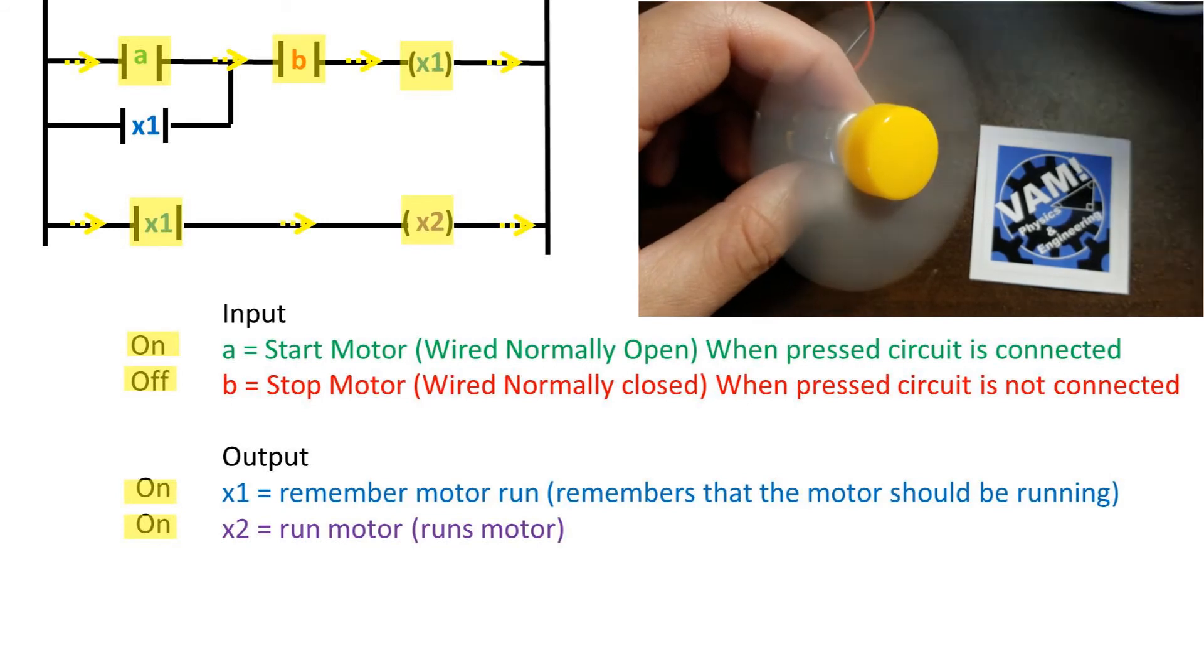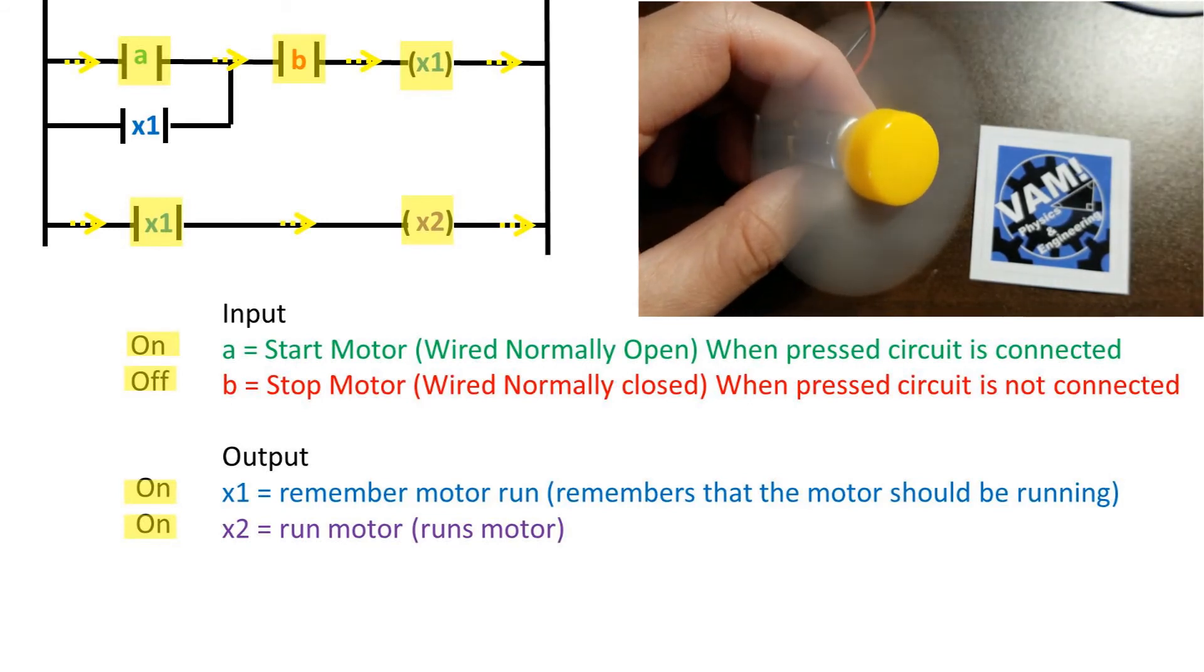Now let's see what happens when we press the start button. Power flows through the A and B contact to the X1 remember coil. On the next rung, the X1 contact is energized, which energizes the X2 motor run coil.